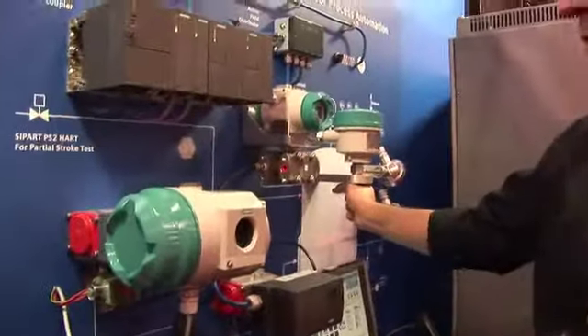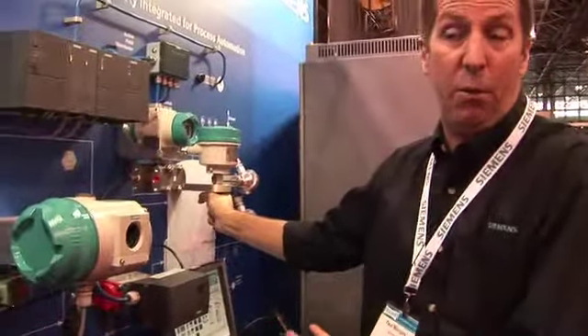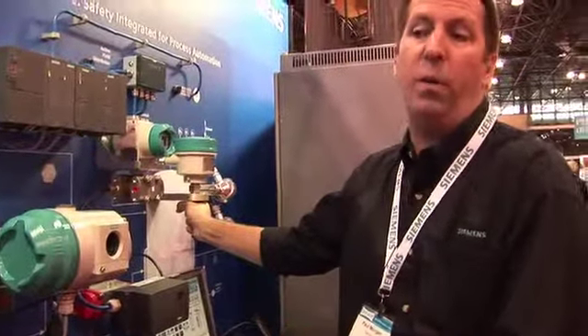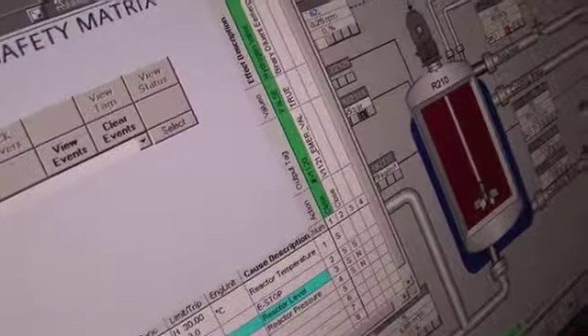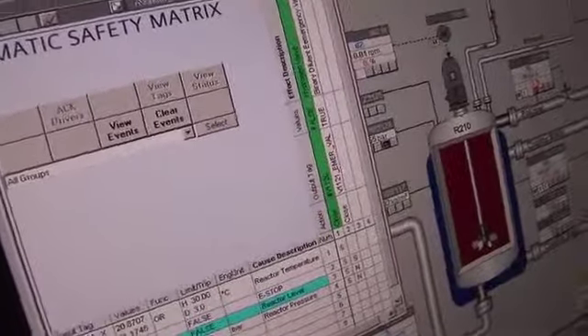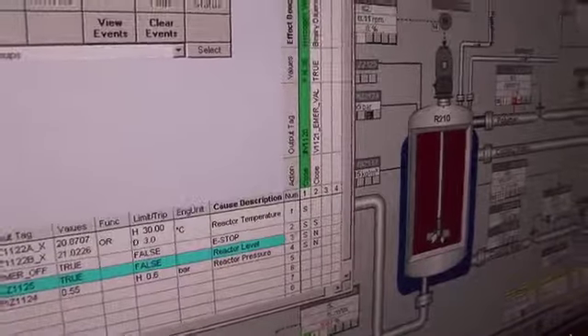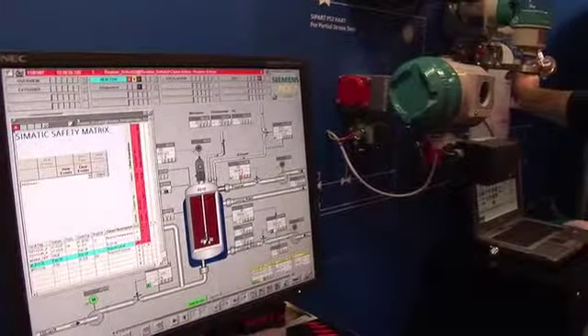I'll trigger the trip condition right now on the level transmitter. I caused a condition where we had an overflow condition that was getting ready to occur within our reactor. It became red — that was indicated by our safety matrix. I just let go of the level switch. Let me hold it here for just one second — we'll get it back to the normal state.